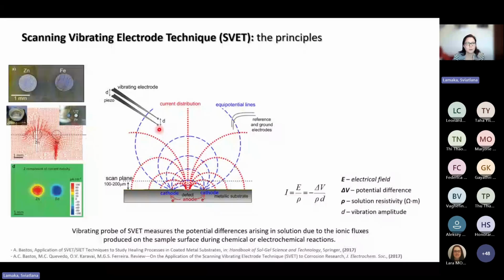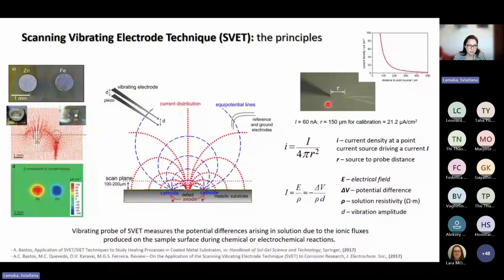And then after the vibration frequency and vibration amplitude are fixed, we perform the current calibration. This is done based on this equation: if we drive 60 nanoampere current at this distance, we expect to reach 21.2 microamp per square centimeter current density. So basically, SVET registers outbreaks and suppression of local corrosion.